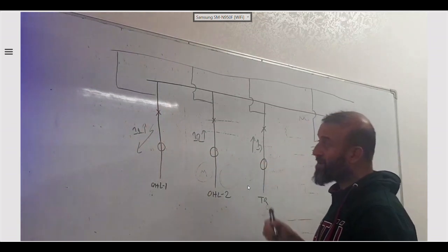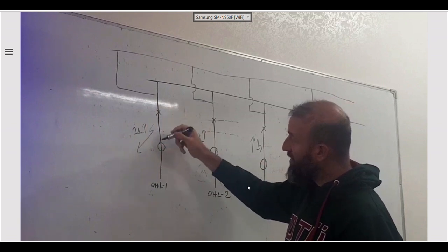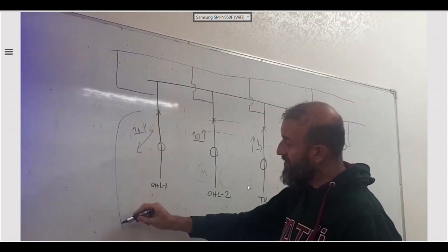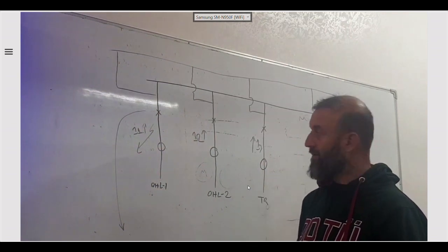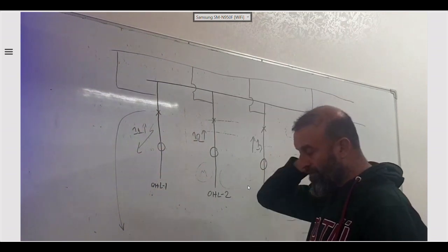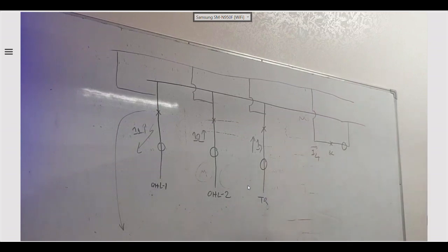But instead, what does it do with the end fault protection? It says that still there is something wrong here, so better I send a teleprotection signal to the other end of the line and clear the problem. So this is one case. For any cases of end fault protection, the circuit breaker must be in open position, definitely.